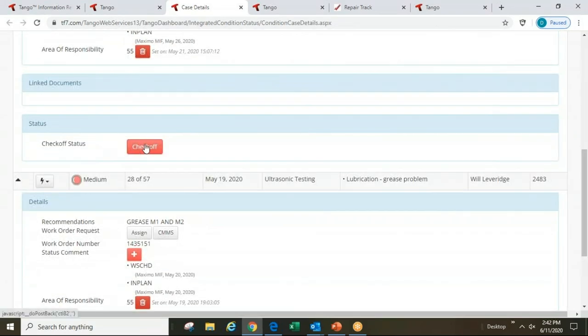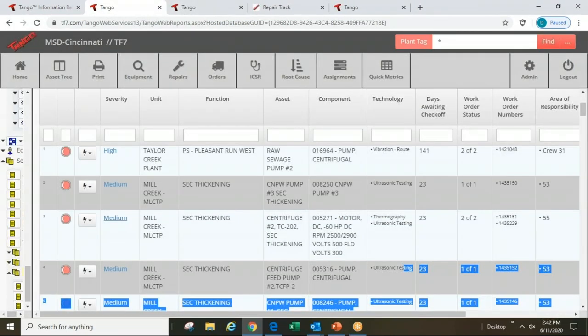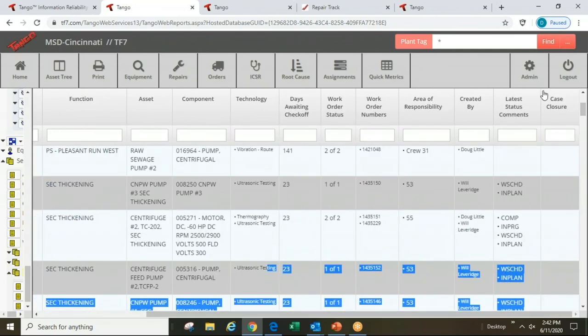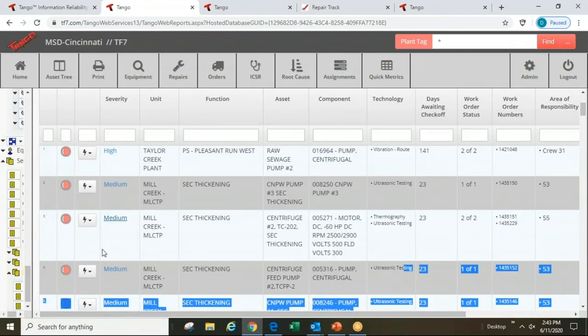In that case, we would use a technology called checkoff — which can be automated. You can create links between the cloud database and the work order system so that when a work order closes, it can automatically do the checkoff on each open work order. Checkoff then sets a closure button — it's a two-step validation process. We know work has been completed, but we don't want to remove this problem from the dashboard until the vibration, ultrasonic, or thermography technicians have gone out, re-inspected, and confirmed no problem remains.